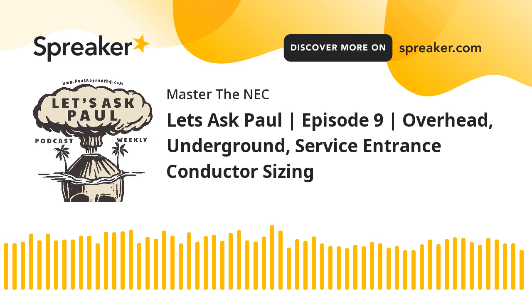I mean, let's say I had 6 of them at 200 amps. That's times 6, that's 1,200 amps of breaker ratings. But what if the calculated load was only 400 amps? Well, then I would size my conductors based on the 400 amps, even though the sum of all the devices would exceed the ampacity value of those conductors. You with me? I'd be very careful with that, but that is what it's saying. Okay, and that's exception number 3.